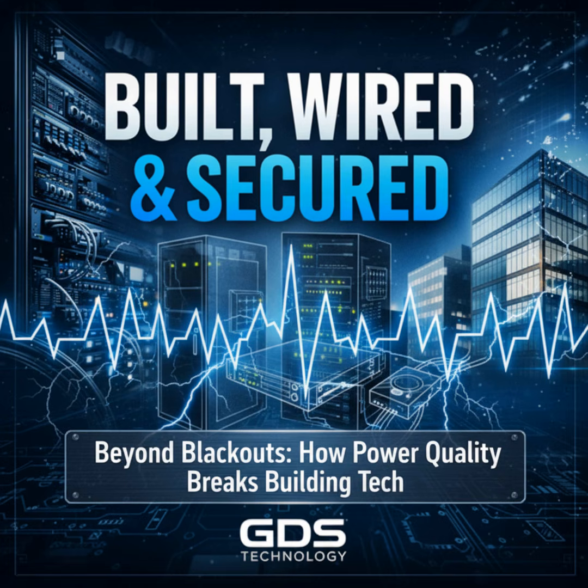Those are great examples. For teams listening and trying to prioritize next steps, what are 5 clear actions they can adopt right away? 5 practical actions. 1. Add power quality checks to regular maintenance. Include quick voltage checks and infrared scans in your PM program. 2. Correlate UPS and BAS logs with tenant incident timestamps before assuming equipment replacement is needed. 3. Use temporary power quality loggers for 24 to 72 hours during peak operations to capture sags, spikes, and harmonics.